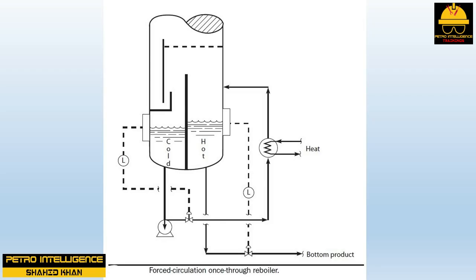A once-through forced circulation reboiler uses a pump to force circulation rather than relying on natural or thermosyphon circulation. This extra pump seems wasteful, but the great advantage of forced circulation is that careful calculation of the pressure drops through the reboiler and associated piping is not critical. However, the operator now has two tower bottom levels to control.